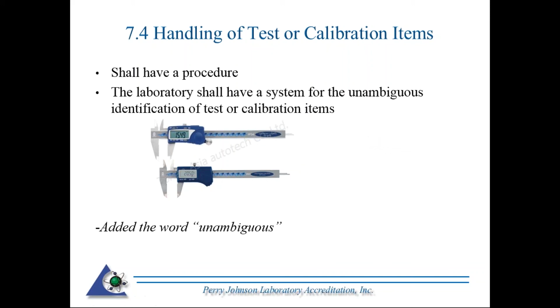So 7.4.3, that's verbatim right there on the screen. I'm going to go over just the highlights of this. Any deviations from specified conditions shall be recorded. These are what we're talking about specifically with environmental conditions. Ask the customer for further instructions and record the results of the consultation and exclusion. So basically, if your method specified, for example, that you would calibrate or test under 20 degrees plus or minus 3 degrees C, and your customer's facility is at 25 C, that's going to force a deviation. Hence, this needs to be discussed with the customer, and if the customer wants you to proceed, it has to be recorded on your results, as you'll see when we get to that section.